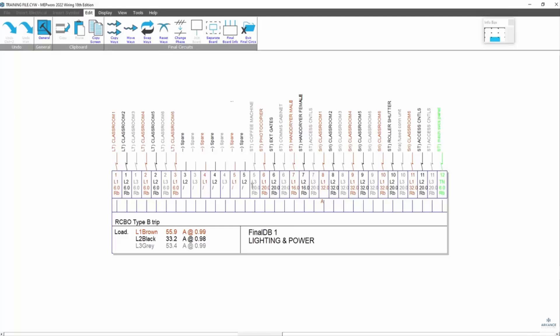You can see here I've got two spare ways that I could have used on the lighting circuit, but I've got this stationary equipment load on way five L3. So I need to drag the other L1 and L2 into the mix. I need to split the board that way.